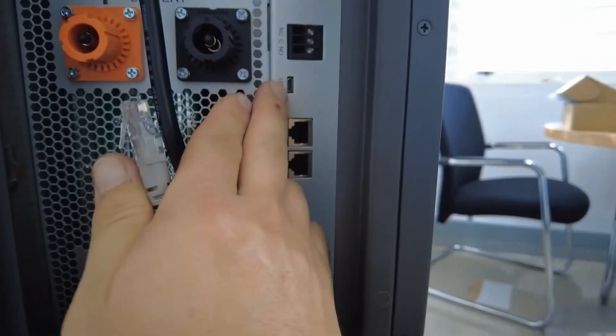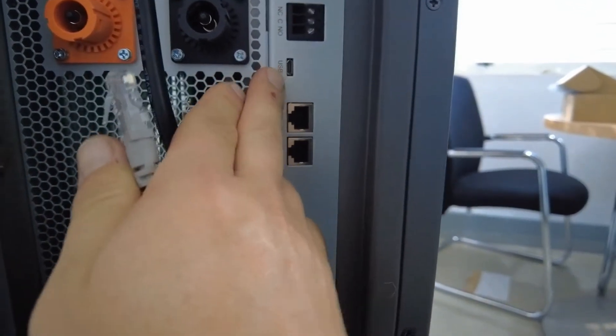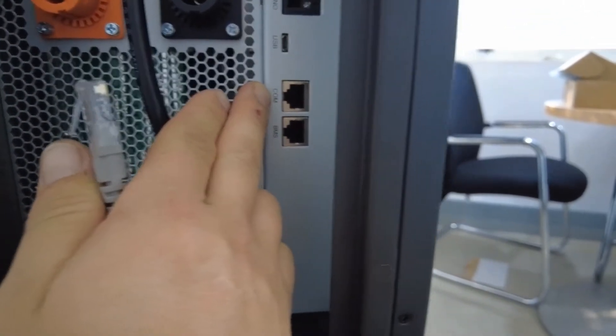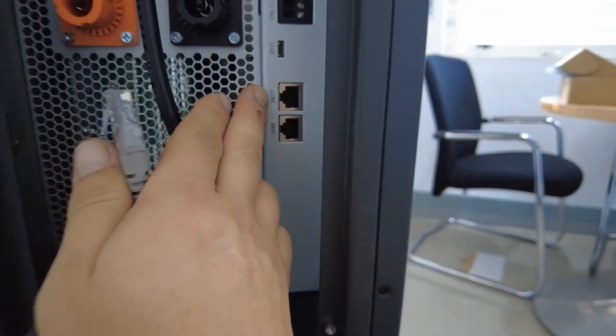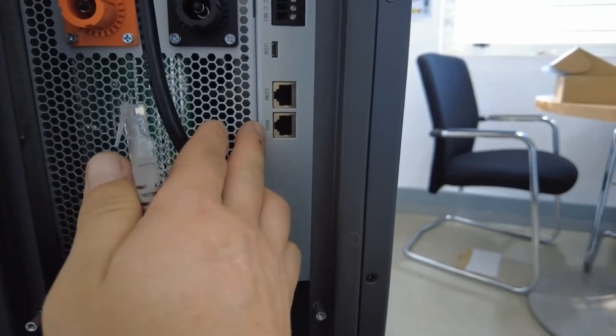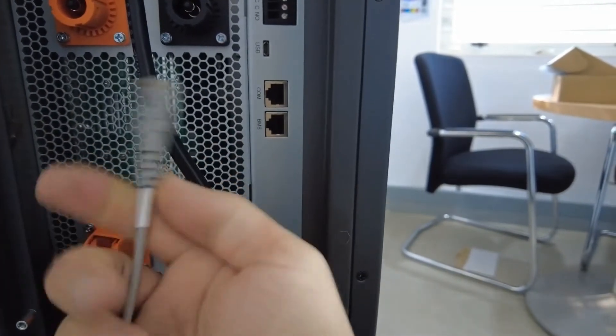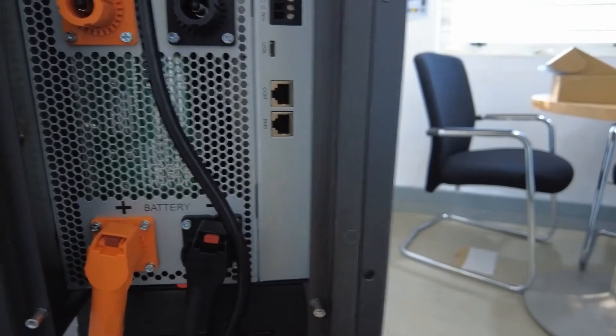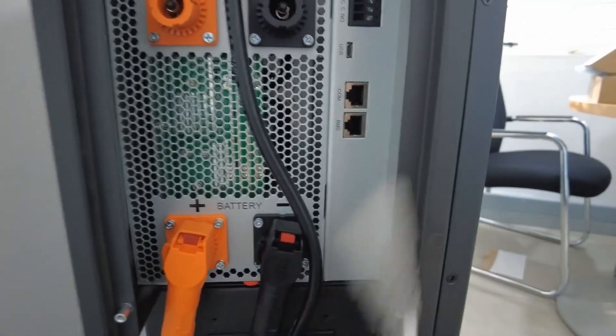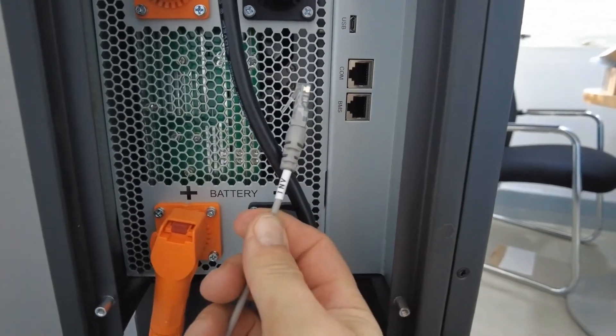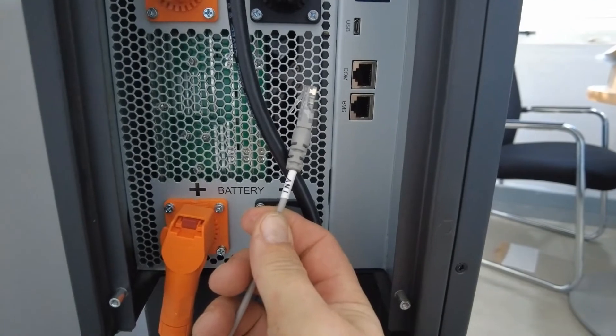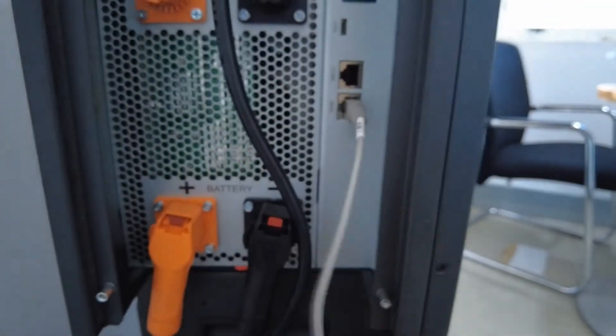Coming down, you'll have your USB port over there, your comms port for your computers, and then the BMS port on the inverter. Look for the cable marked as inverter, INV. This is the plug you need to connect to the BMS port.